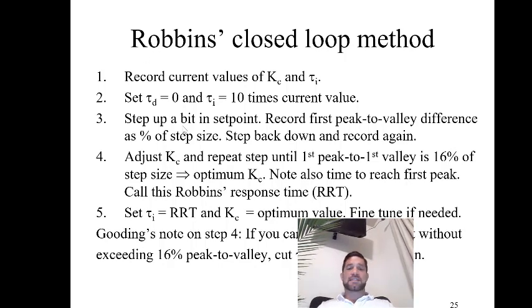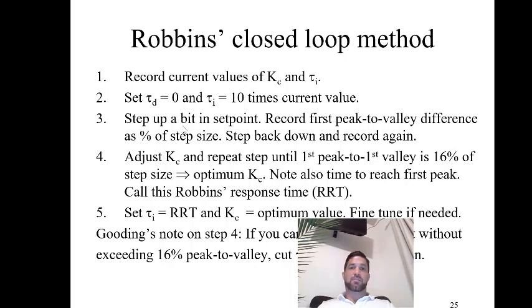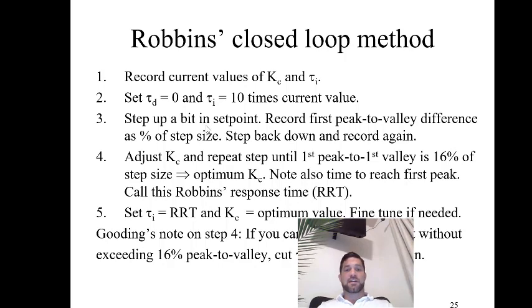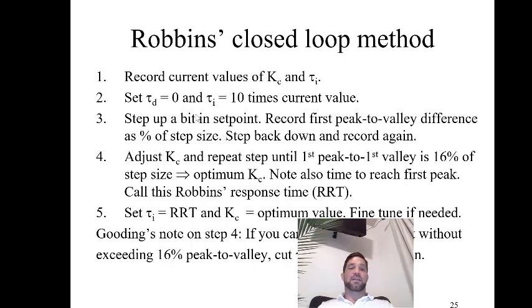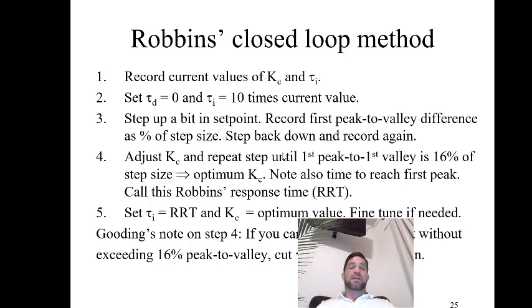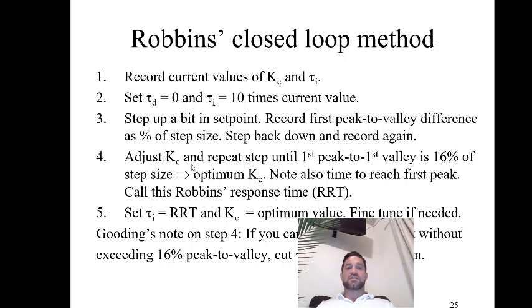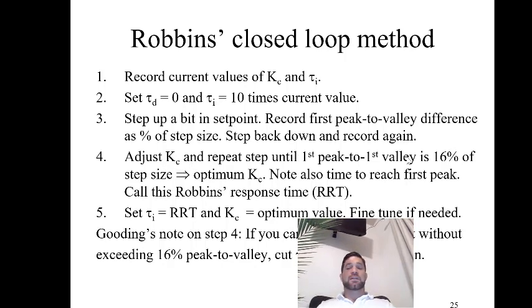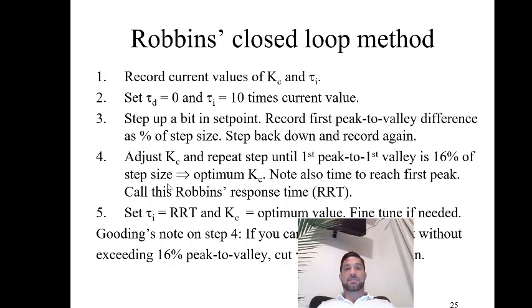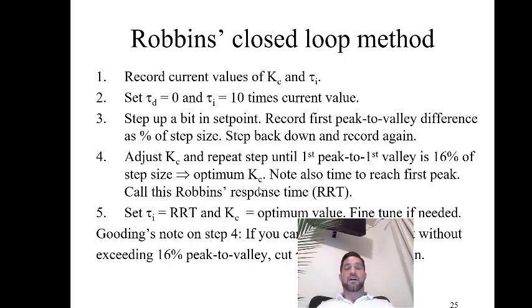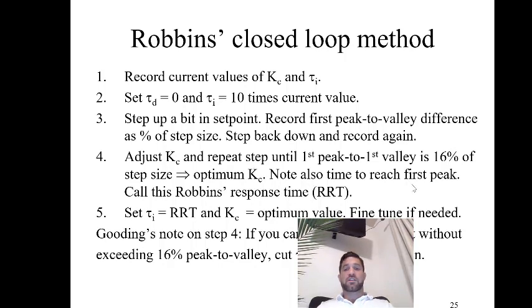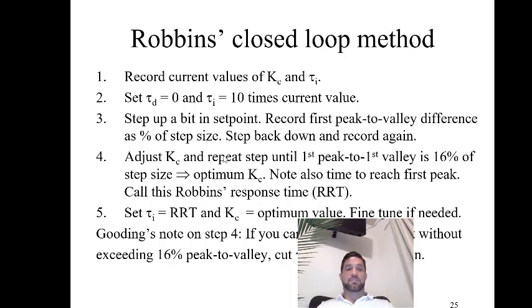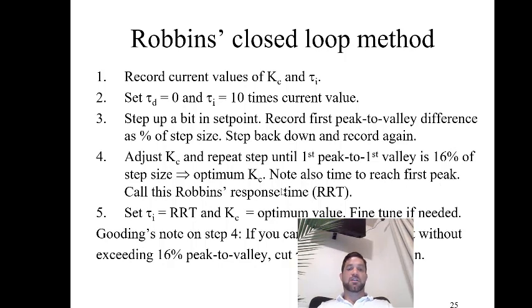Then we're going to step up in the setpoint and step down and look at the process response. We're going to record the first peak to valley difference as a percentage of the step size for both going up and down. Then adjust the KC until the first peak to valley is about 16% of the step size. This is going to be our optimum value of KC. Also, we're going to record the time from when we apply the step change to reach the first peak. This is called the Robbins response time.